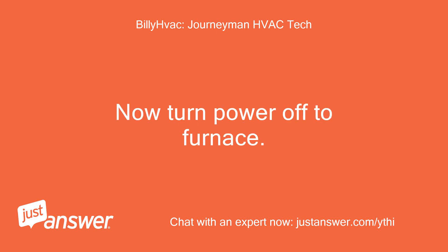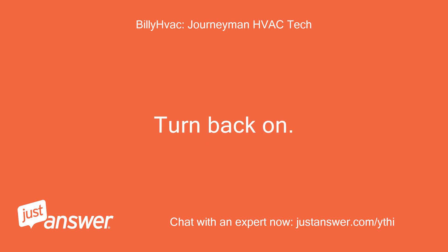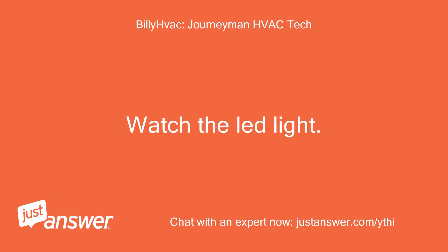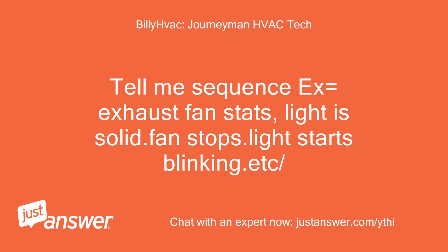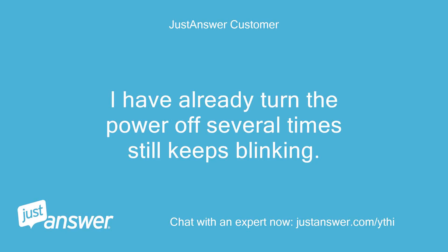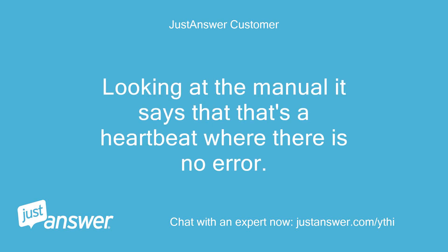Now turn the power off to the furnace, then turn it back on. Watch the LED light and tell me the sequence — for example, exhaust fan starts, light is solid, fan stops, light starts blinking, etc. I have already turned the power off several times and it still keeps blinking. Looking at the manual, it says that is a heartbeat, meaning there is no error.